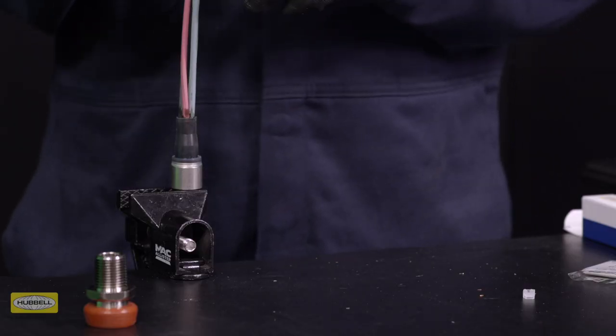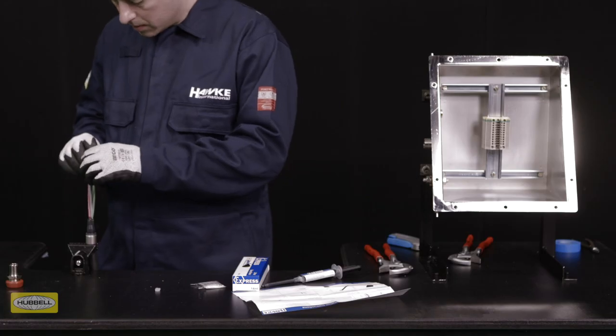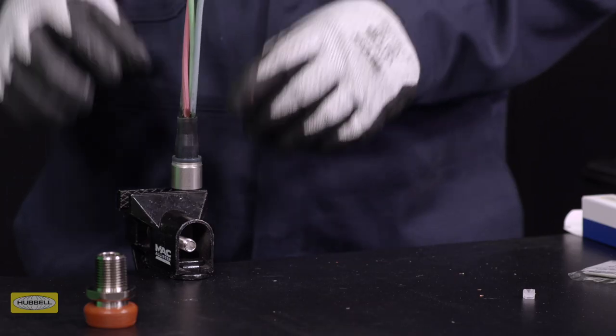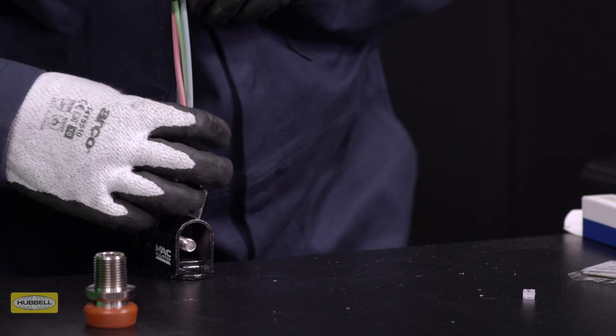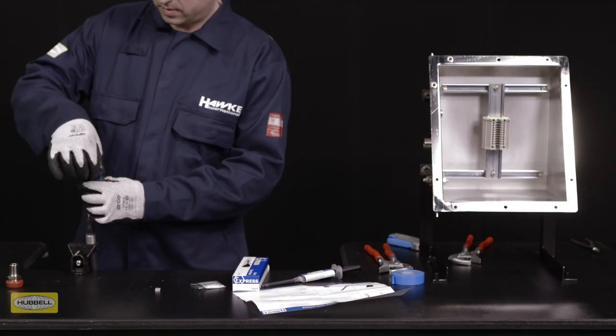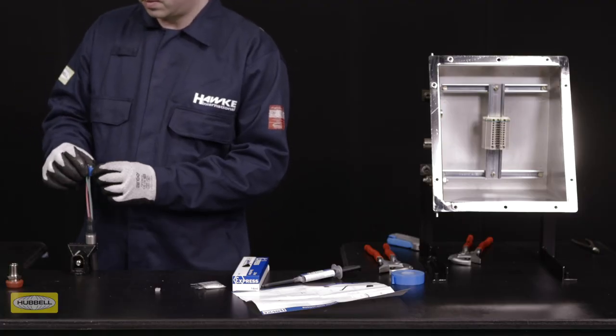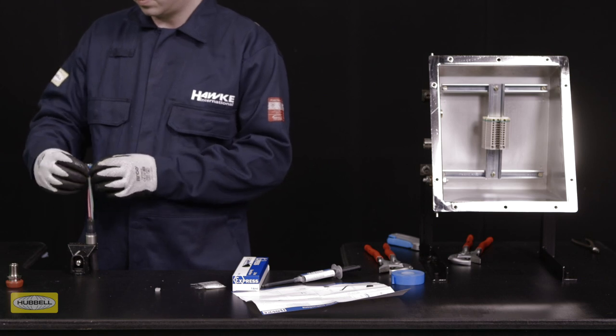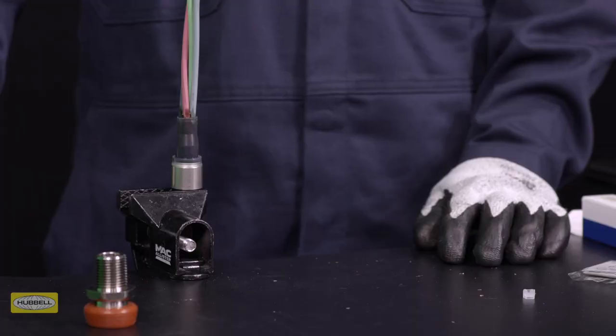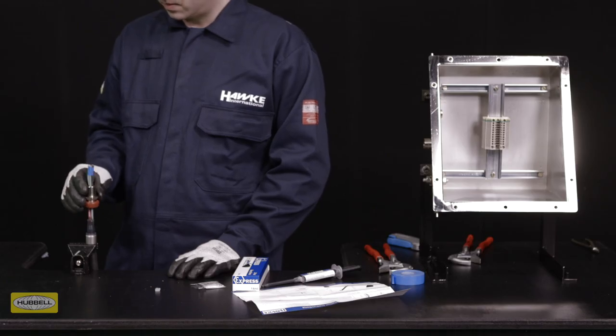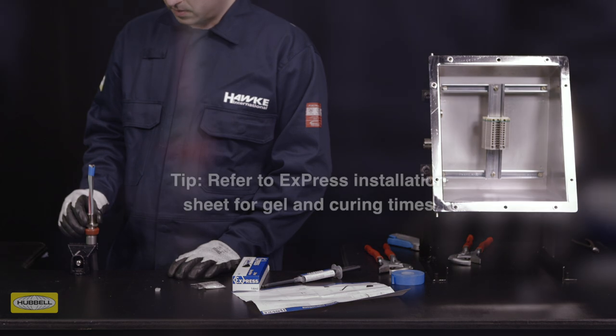Manipulate the cable cores to ensure the resin has filled any voids between them. If air pockets are present, coax them out from the resin by manipulating the silicon pot. Tape the cores so they stand centrally to the pot. If the fill level drops below the minimum level, top up the resin to the fill line. Place the entry over the silicon pot to ensure it is held in the correct position. Gland installation can now continue.